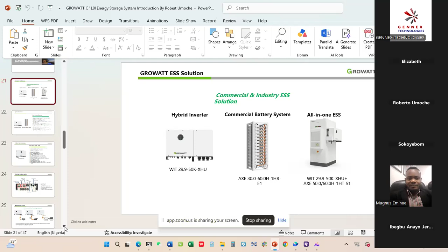Anytime you are commissioning our C&I solutions, just like a quick guide, a quick set, you can easily connect through your data logger. So you go to the battery settings. If you enable BMS 1, your battery bank number 1 connected will be detected if the communication is established. Then if you go to BMS 2, enable, BMS 3, enable, and then the 3 batteries will be meshed together. They charge uniformly and discharge uniformly. Then the only difference between this battery and this cabinet is in the cabinet, but this battery, if you go further, you will see the internal structure of this one. What you have here, you still have here, but this one is in the cabinet, and this one is without cabinet. Next slide.